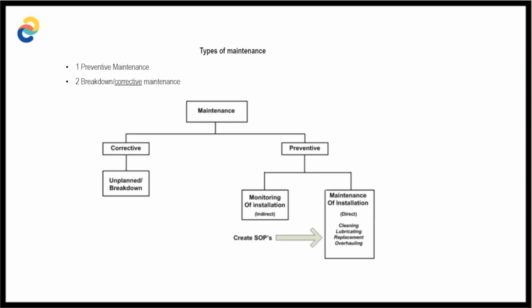Okay, so generally, we have two types of maintenance. One is corrective and one is preventive. Corrective means the activities which are carried out after the occurrence of failures to correct the failures. This can also be referred to as unscheduled or unplanned maintenance. Some examples of that are cases wherein we have experienced a flooded compressor, burnt motor, or passing of valves.